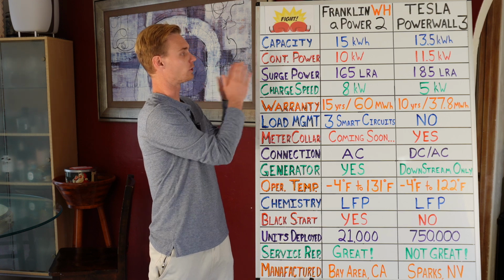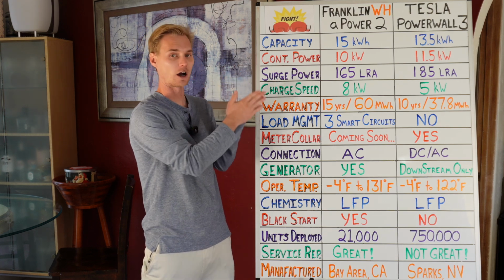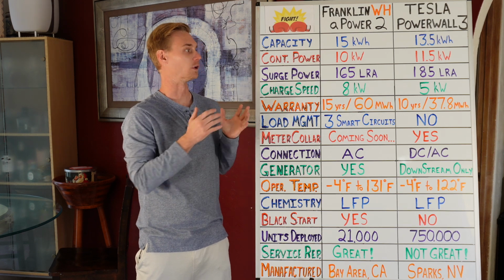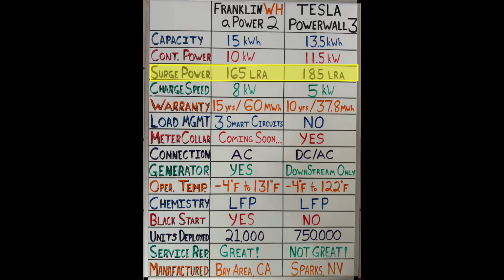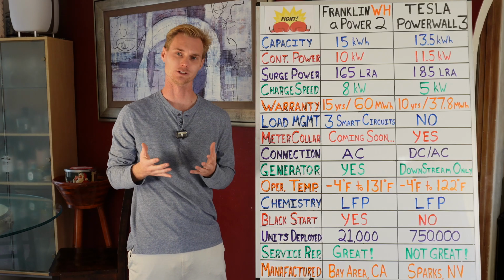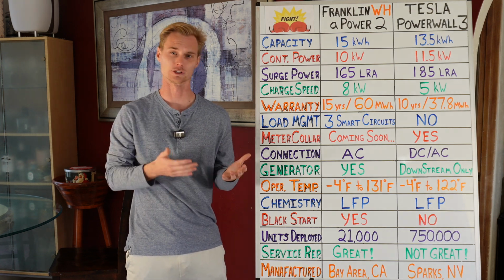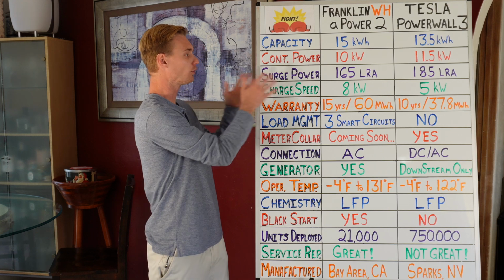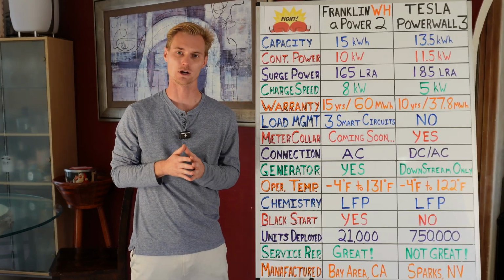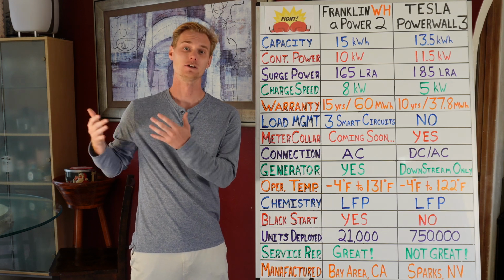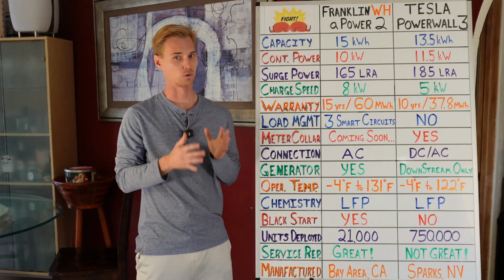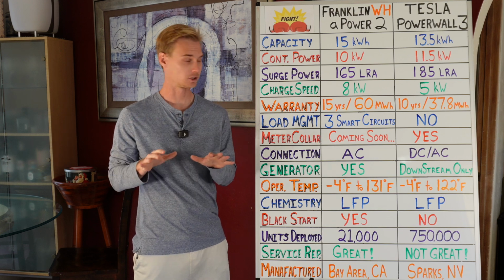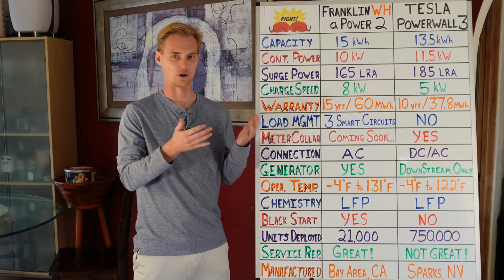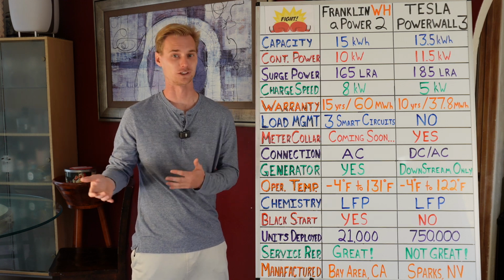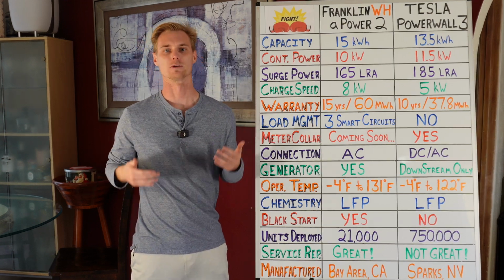So the continuous power is slightly higher on the Tesla Powerwall 3, which is a win for the Tesla. Same thing with surge power being 185 LRA - that stands for locked rotor amperage, essentially how much power is required to start something like an HVAC machine. With both systems, you should be able to start either a 4 or maybe a 5-ton HVAC system, so you should be okay with one battery in most scenarios, but with just one battery running an HVAC or similar, it may not last very long - that's when you'd want maybe 2 batteries.